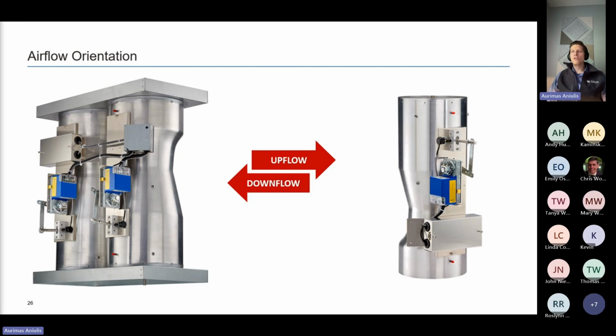Now, orientation is also key for Venturi air valves. That's another kind of drawback, you could say, of this technology, where the cone spring assembly is not impervious to gravity. And at the time of selecting equipment, you should know whether it's going to be installed in an upflow or a downflow position or a horizontal position, because that's part of the configuration of the device that you'd have to order. And in the factory, we will calibrate it vertical up, vertical down, or horizontal, and it cannot be replaced in the field. We had a customer that ordered $50,000 worth of air valves only to realize he ordered the wrong orientation. Don't do that. Not fun for anyone.